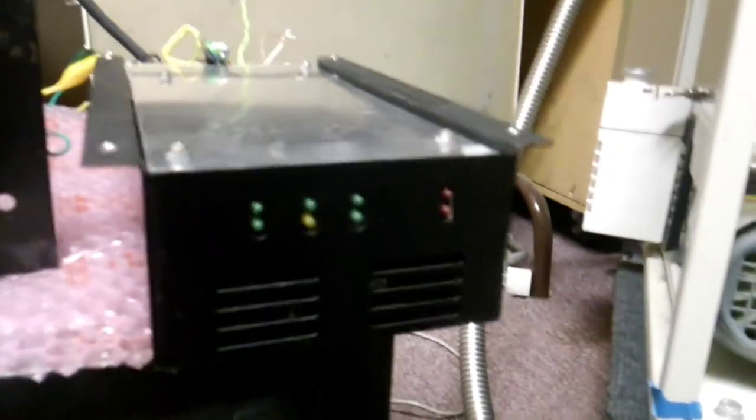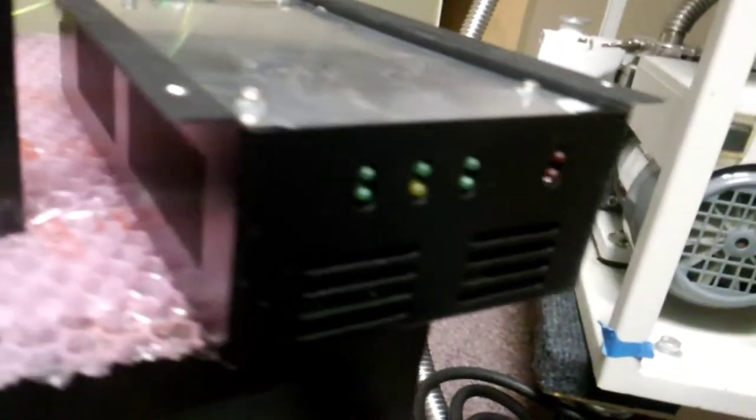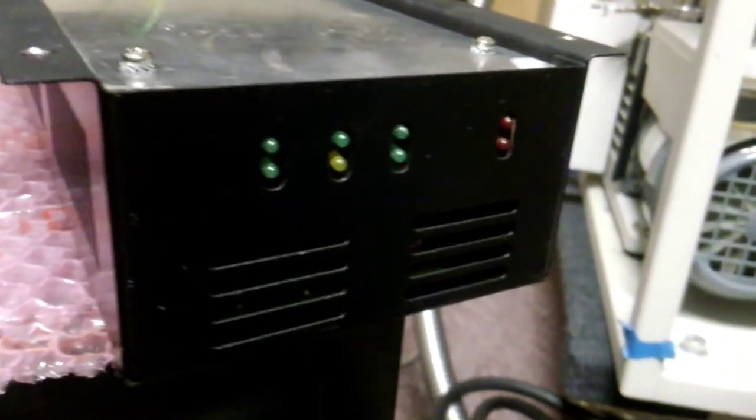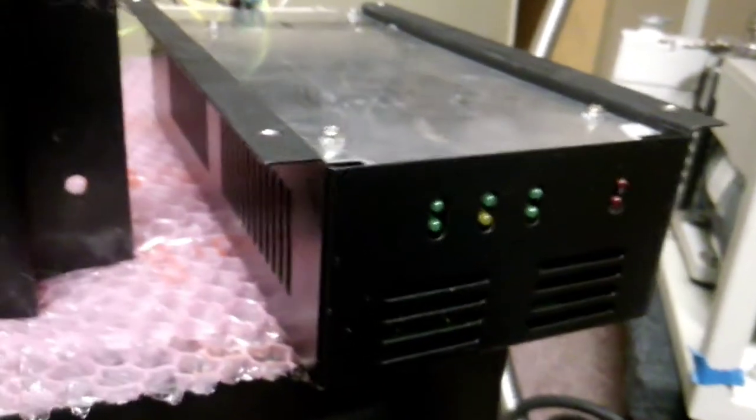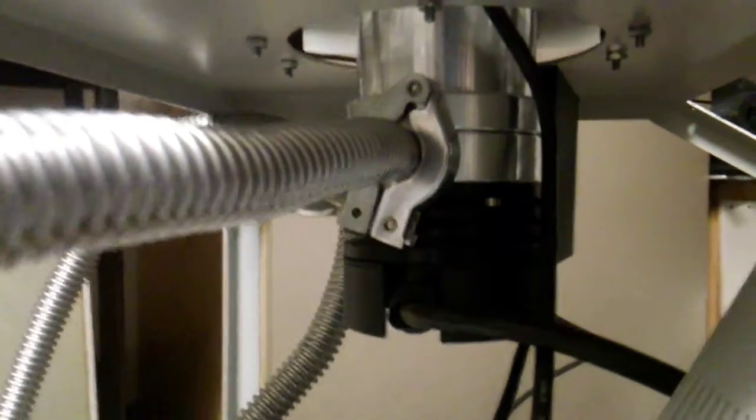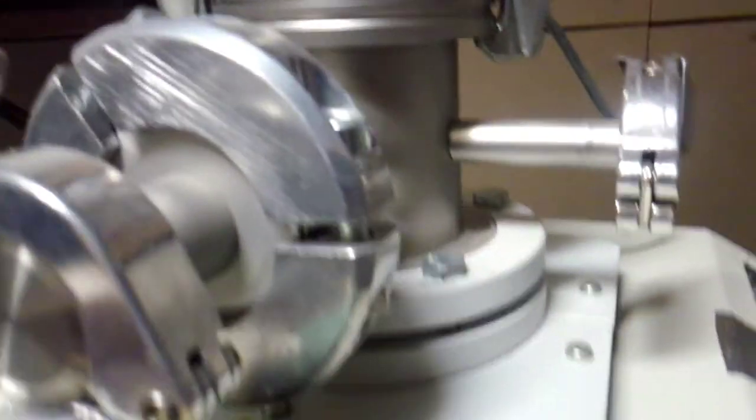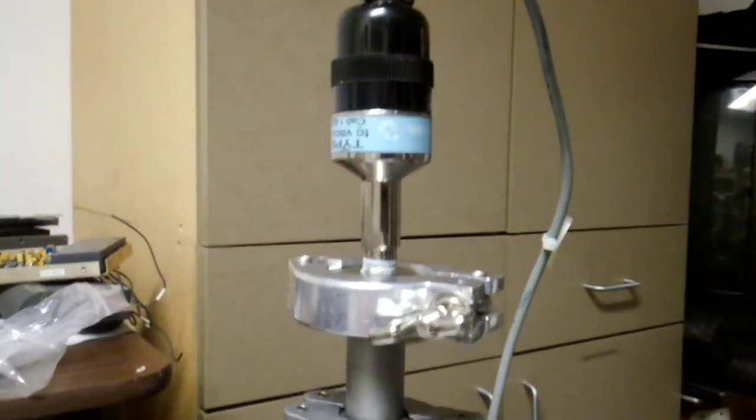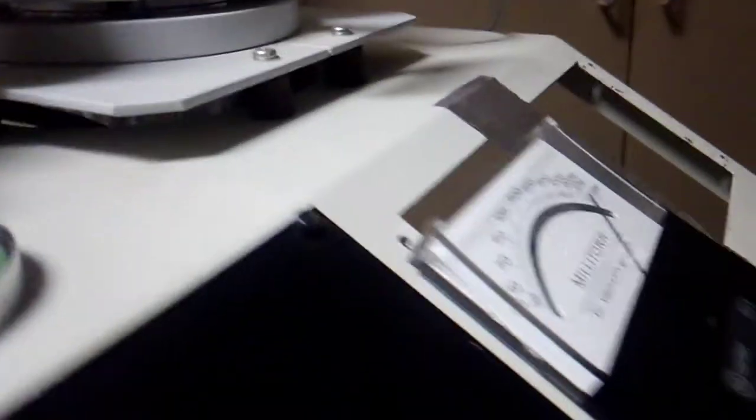Okay, here's a turbo pump controller that goes in the fine focus x-ray machine at DCX. I've got it powered with a variable transformer set to 110 volts AC, and I'm powering this turbo pump, Leybold Heraeus pump, which is the proper size for that, backed up by this small mechanical vacuum pump. On the inlet side of the turbo pump I have all this apparatus with a vacuum gauge, and I can read here on this thermocouple gauge display.